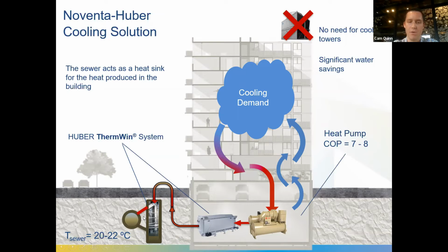So we have what we call a wet well, which is tied into a sewer, and we pump sewage from the sewer to the other side of this heat exchanger to heat it up so the heat can be rejected from the building, and then it comes back to the sewer. We'll go into more details on that in a second. The important thing here is, again, the sewer is acting as the heat sink instead of the atmosphere. Normally sewer water is in the, let's say, 20 to 22 degrees, maybe a 20 to 25 degree range, and it's water. So it's a significantly different heat sink source than the atmosphere that the cooling tower was using.